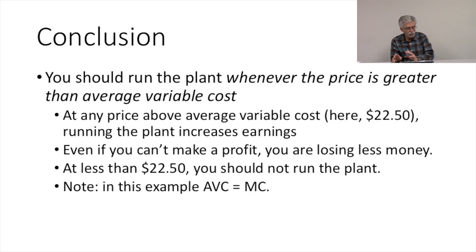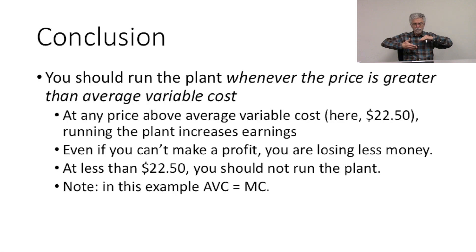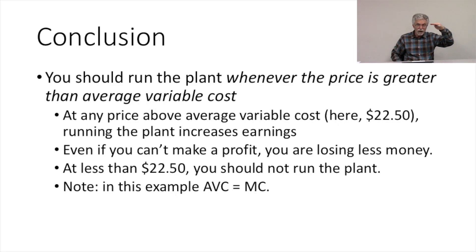So what is our conclusion? You should run the plant whenever the price you can get is greater than the average variable cost. If your price is lower than the average variable cost, you would turn the plant off. If the price offered is greater than the average variable cost, it's worth running it because you're making up some of those fixed costs — you're losing less money. If you can't get more, it's still worth running the plant because you'll be paying some of those fixed costs.